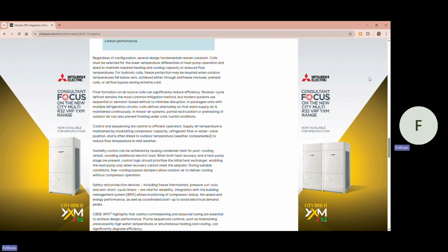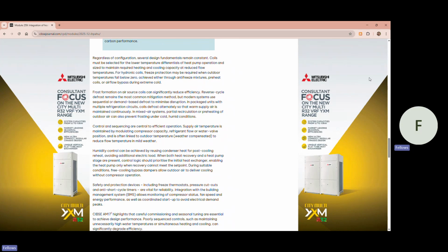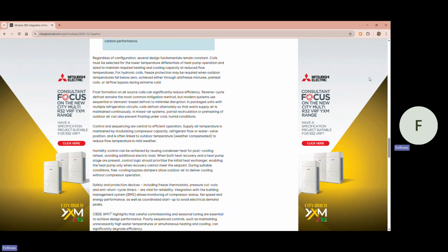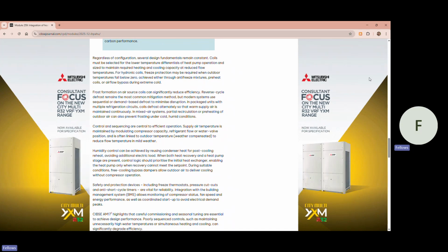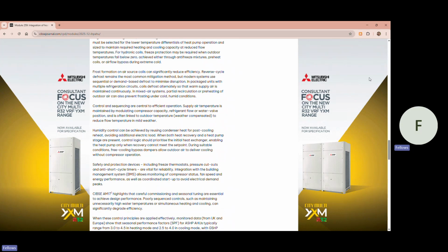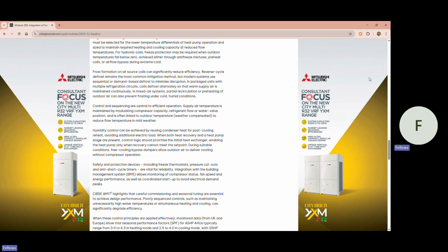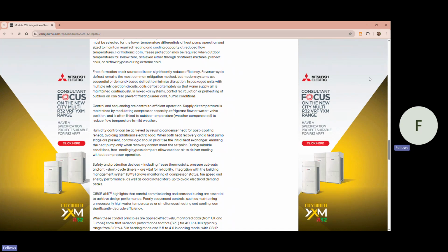Control and sequencing are central to efficient operation. Supply air temperature is maintained by modulating compressor capacity, refrigerant flow, or water valve position, and is often linked to outdoor temperature, weather compensated, to reduce flow temperature in mild weather. Humidity control can be achieved by reusing condenser heat for post-cooling reheat, avoiding additional electric load.